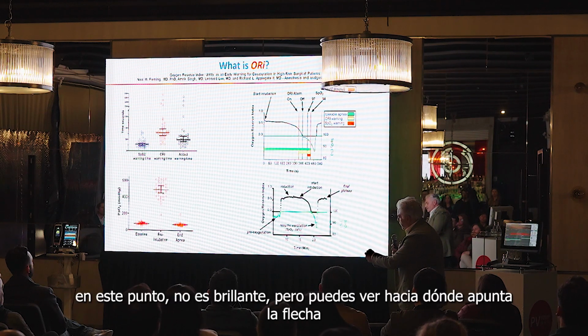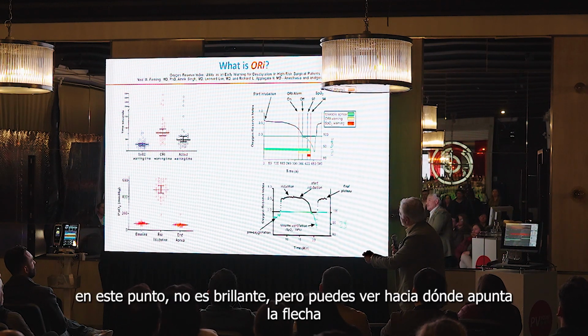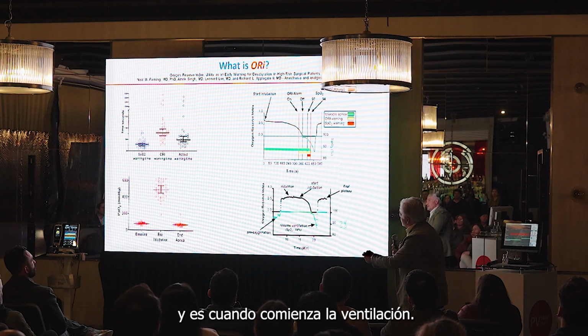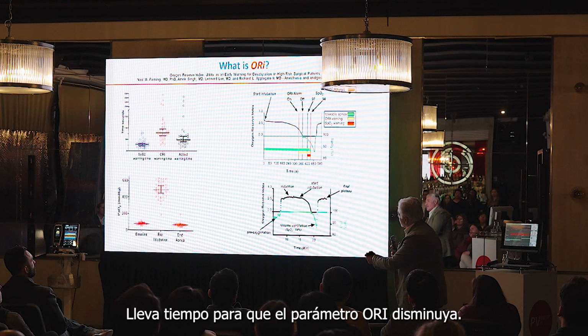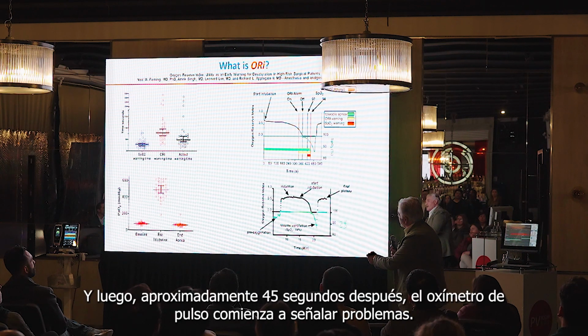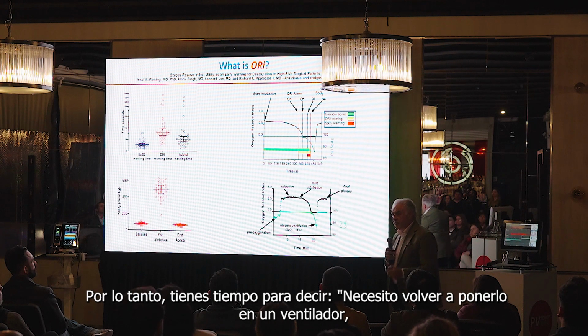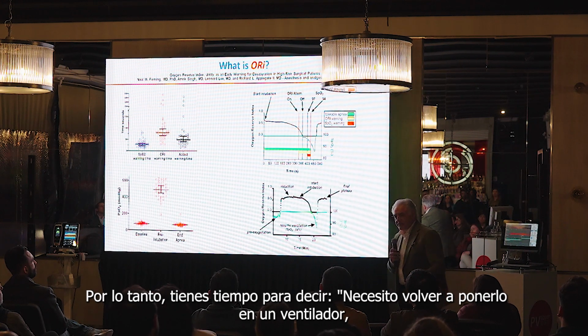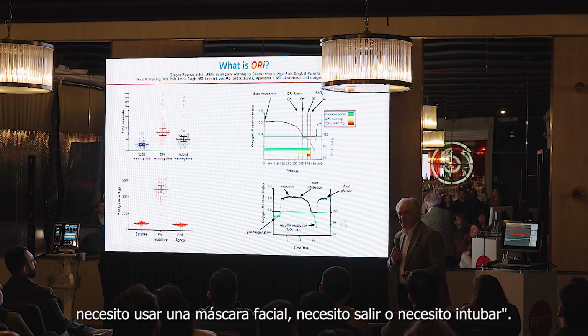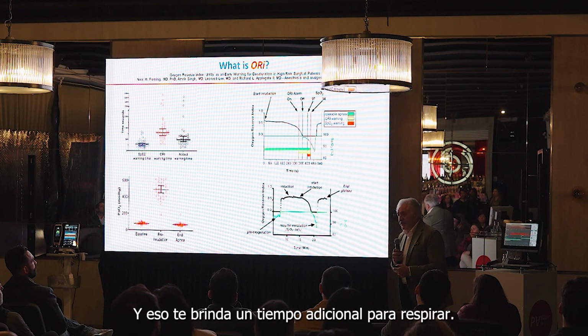so this pointer is not brilliant, but you can see where the arrow is pointing, and it's where the apneic ventilation starts. It takes time for the ORI parameter to drop, and then about 45 seconds later, the pulse oximeter starts ringing. So you have time to say, okay, I need to put them back on a ventilator, I need to face mask them, I need to get out, or I need to intubate. And that gives you the extra bit.